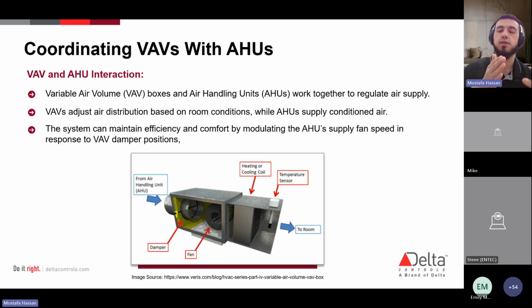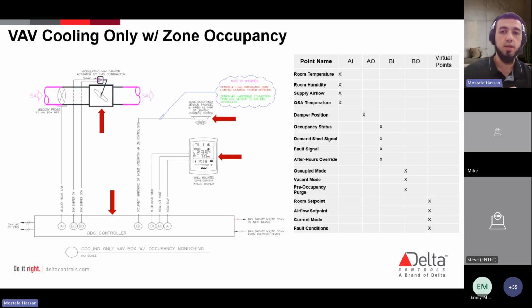spaces, right? Adjusting their damper position to allow specific CFM, whether they want to increase the cooling output in that space or not. So this is a schematic for a cooling only VAV box with zone occupancy monitoring, right? We're going to go through the sequence of operations here together. The sequence of operations is not shown in front of you. I'll read through it, but you'll see some animations that will help you point at the section I'm referencing, okay?